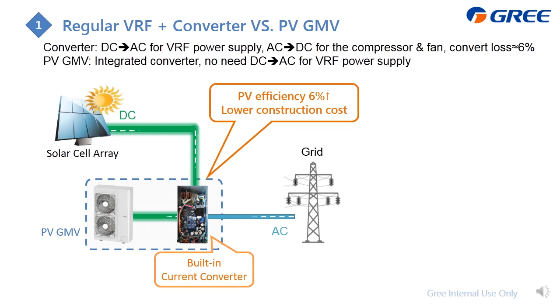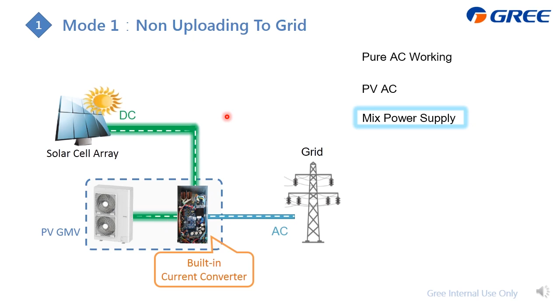This slide explains how this PV-GMV works. Mode 1 is not uploading to the grid, which means you get power from the PV panels only for the power consumption of this PV-GMV. For this system, first it can consume 100% of the power from the grid power supply, acting as a regular VRF. It can also consume 100% of the power from the PV panels. And it can also mix them together, meaning if the PV power is not enough, it can get the insufficient part from the grid power supply. All three of these modes are automatic, with no need to set anything.